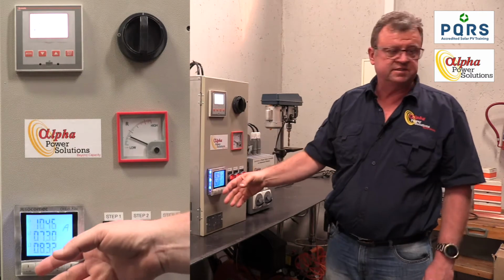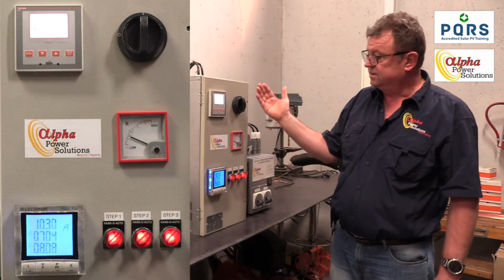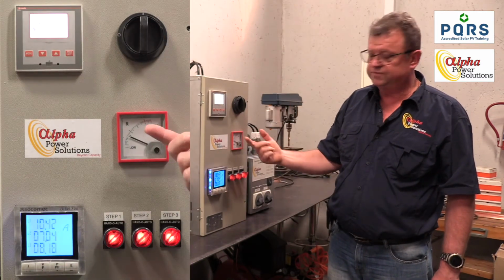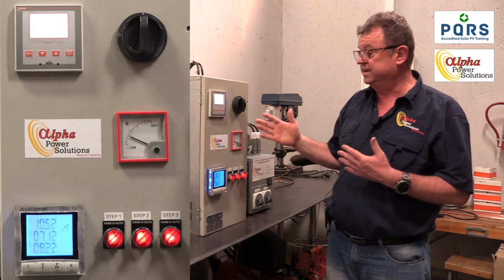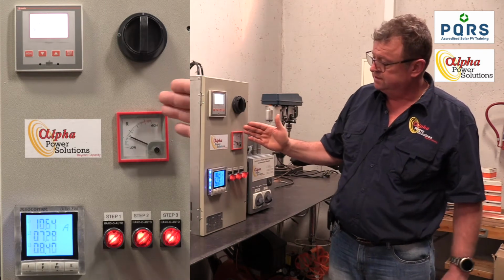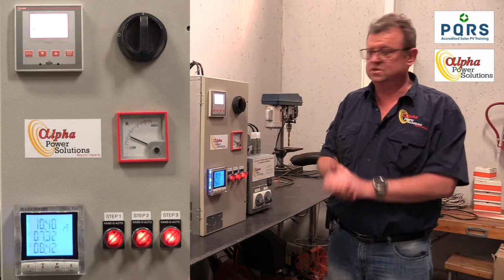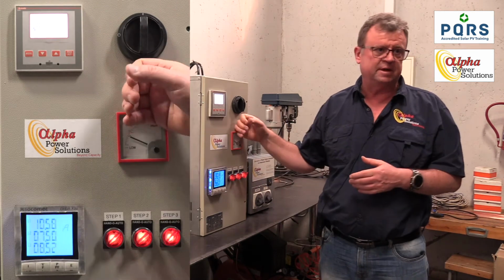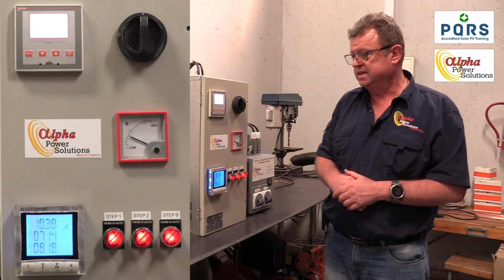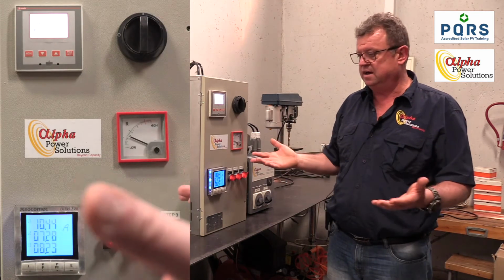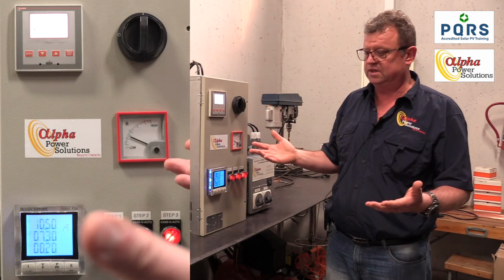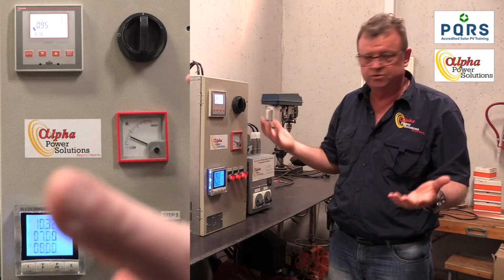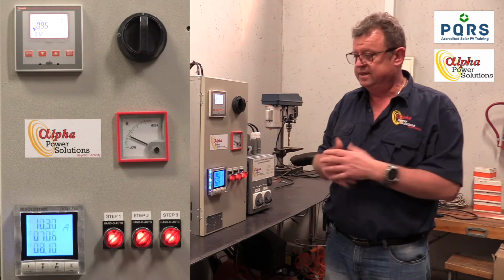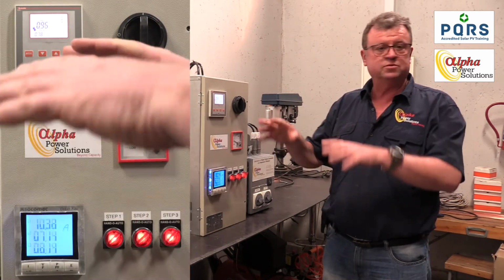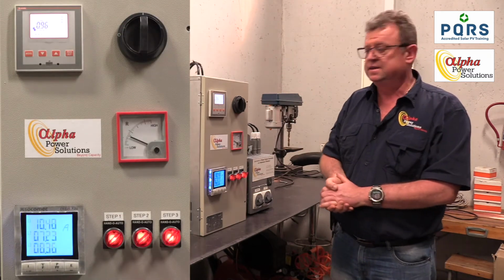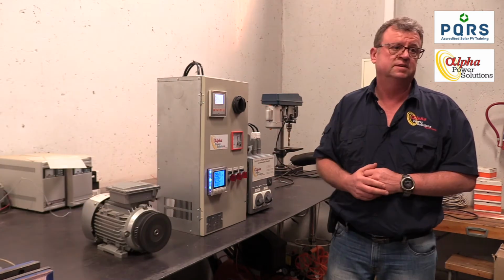The end result is exactly the same. And as you can see, as far as energy consumption or energy charges from Eskom, this has really dropped down because the reactive power is now supplied by the box and not Eskom. So in a nutshell, that is how it works in a factory as well. Obviously, you would have many motors, the load would be very big, and so this would be a much, much bigger panel, but that is the principle.